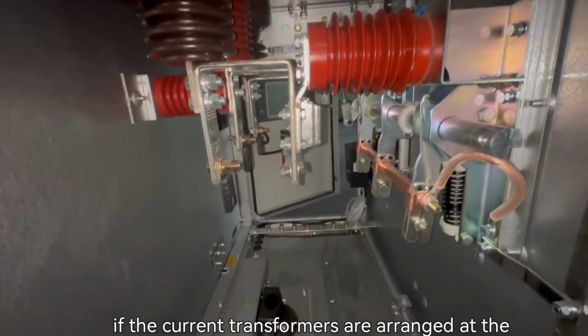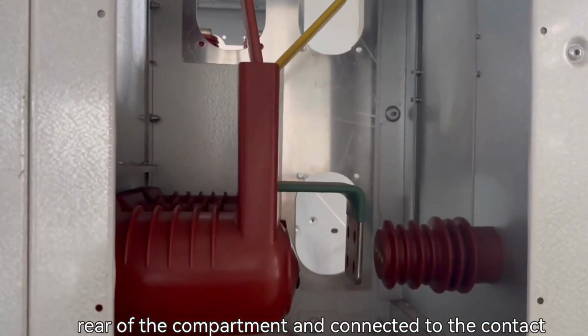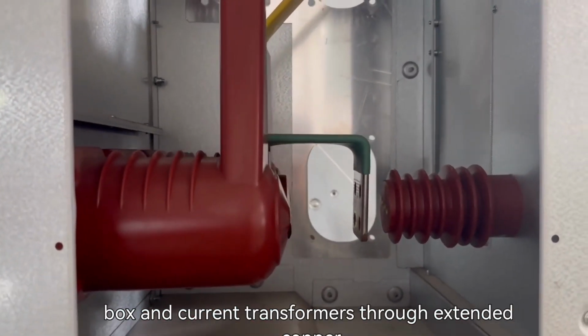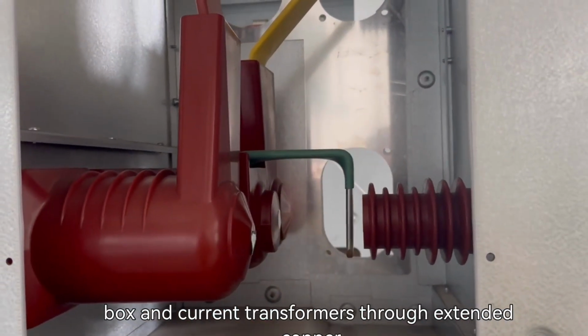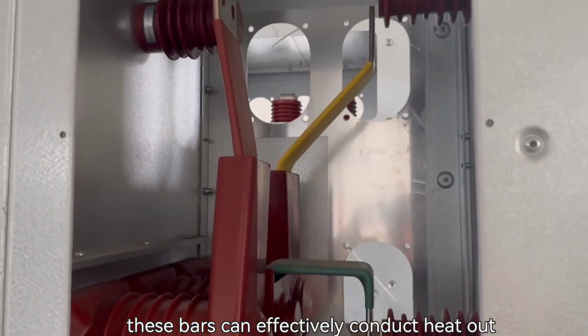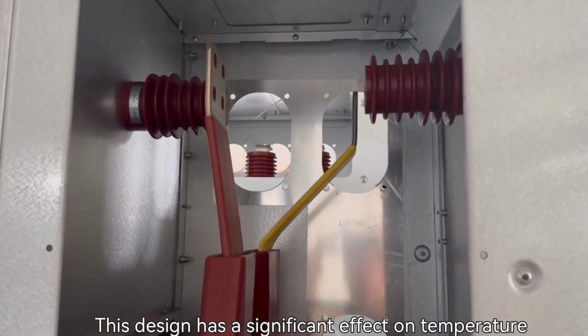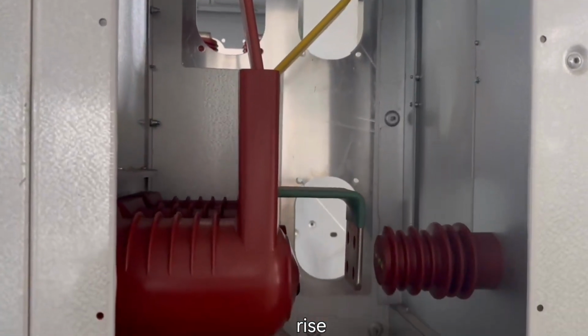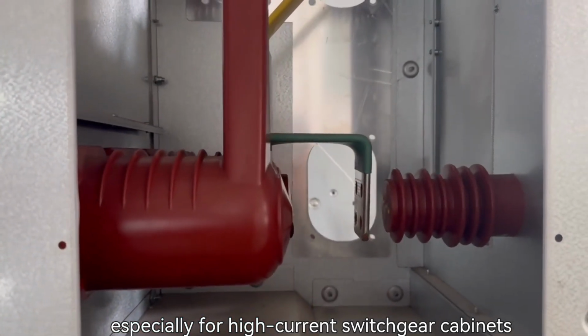However, if the current transformers are arranged at the rear of the compartment and connected to the contact box and current transformers through extended copper bars, these bars can effectively conduct heat out. This design has a significant effect on temperature rise, especially for high-current switchgear cabinets.